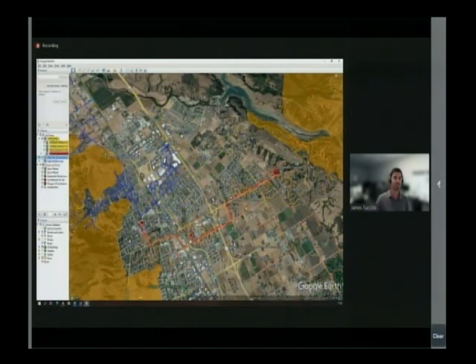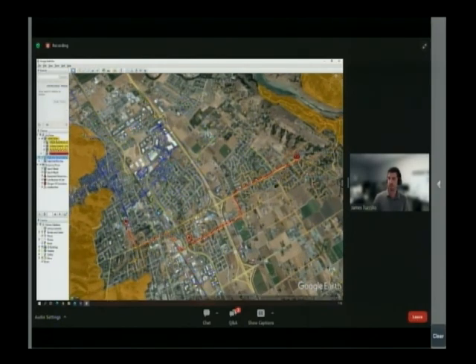These devices help segment the grid so that when we have a failure or an outage, such as a car-pole incident where a vehicle contacts a pole and brings the lines together into a faulted condition, a faulted condition being anything abnormal on the system, these devices operate to interrupt that source of energy so the situation is made safe and de-energized.